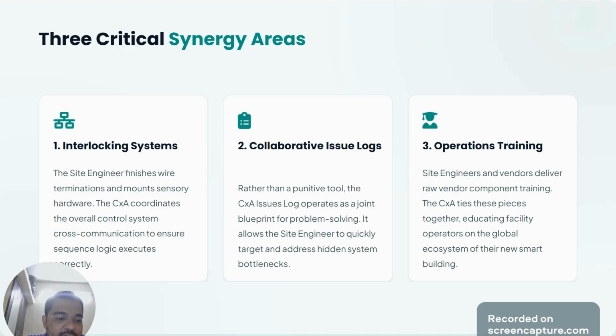Second, treat the CxA issue log as a helpful task list. The CxA issue log is where the CxA identifies shortcomings in the installations and notifies the contractor that these shortcomings need to be rectified. This log should not be treated as a bottleneck or hindrance by the general contractor—it's a helpful task list, not a penalty card. It's a tool to get things fixed before handover.